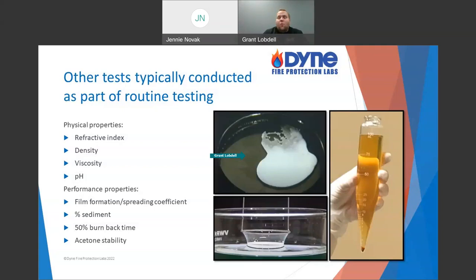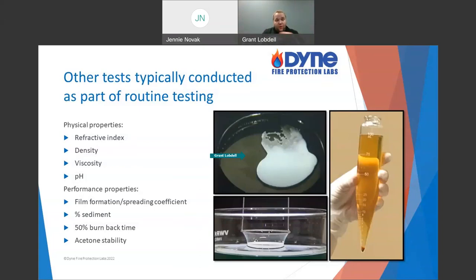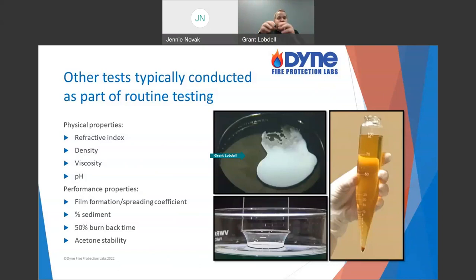Why do we use this film? Who doesn't want more protection? Where this really becomes important is if the foam blanket gets separated — let's say a hose drags across it and sweeps some of the foam blanket to the side. Hopefully the foam flows back and covers it, but maybe not so quickly. But the film is very quick. If I step and lift my foot, the fluorochemical solution that has been slowly draining is actually going to sit on top too, forming that extra layer of protection and flowing right back over the exposed area.